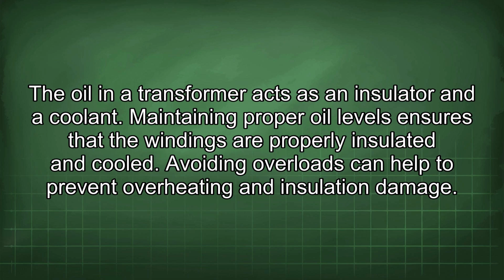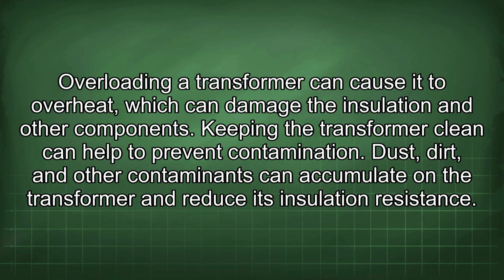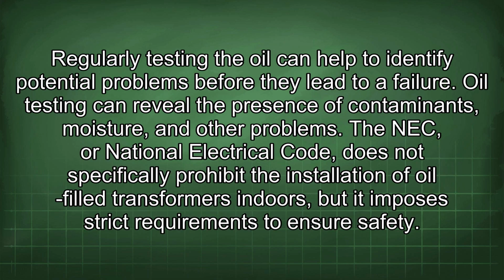Avoiding overloads can help to prevent overheating and insulation damage. Overloading a transformer can cause it to overheat, which can damage the insulation and other components. Keeping the transformer clean can help to prevent contamination. Dust, dirt, and other contaminants can accumulate on the transformer and reduce its insulation resistance. Regularly testing the oil can help to identify potential problems before they lead to a failure. Oil testing can reveal the presence of contaminants, moisture, and other problems.